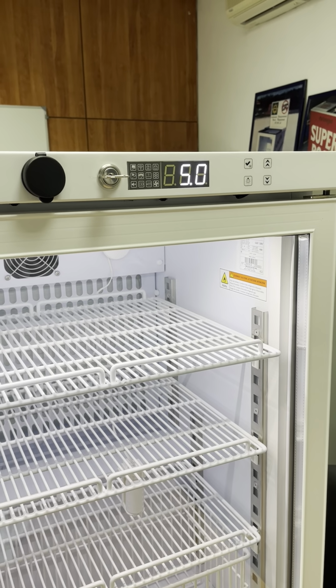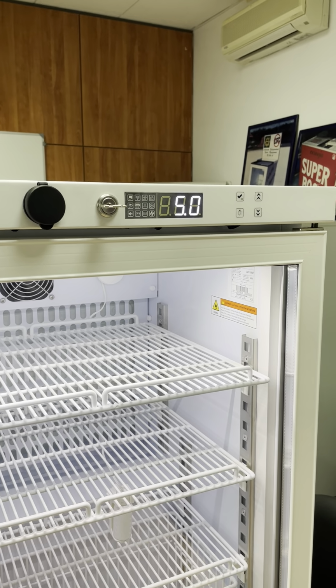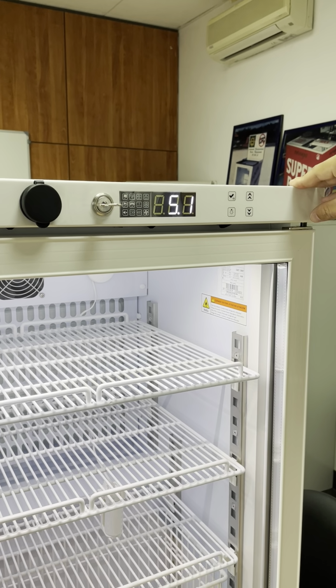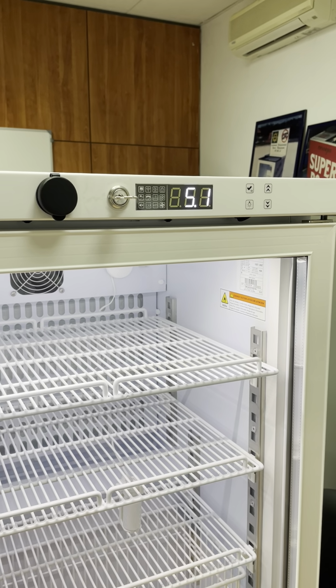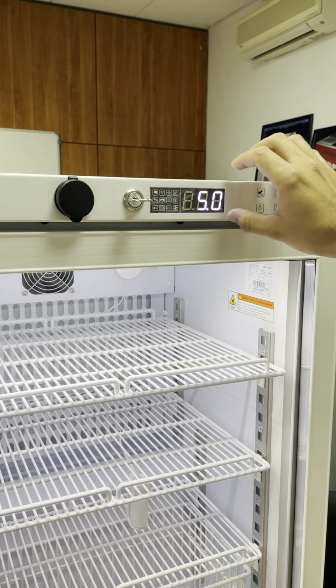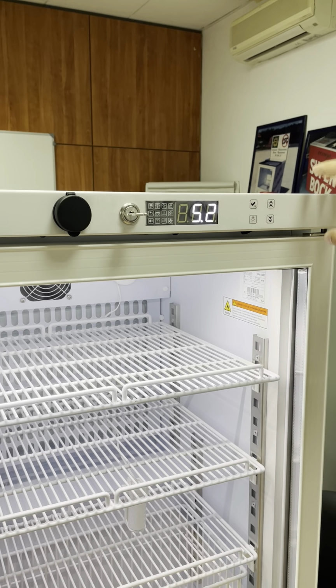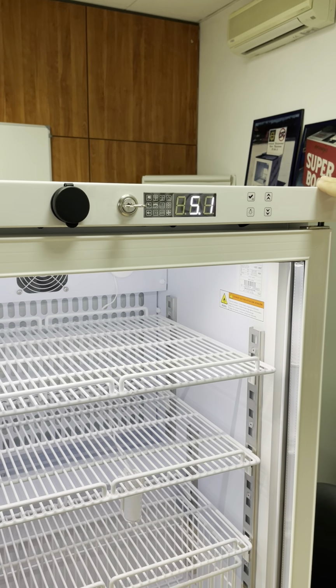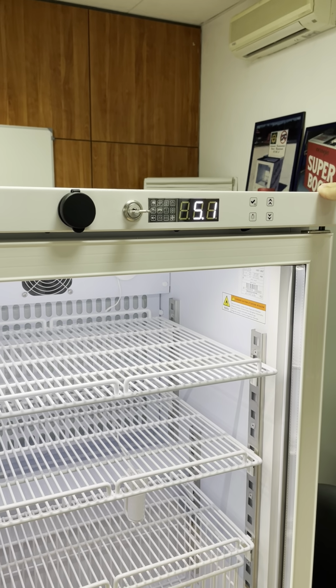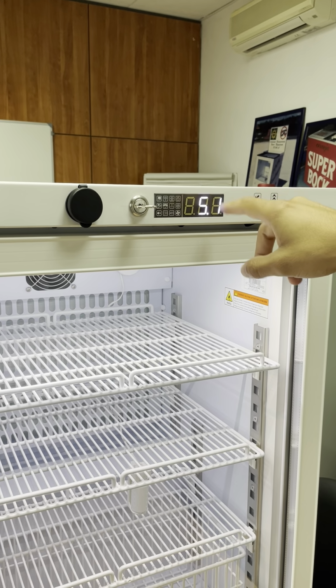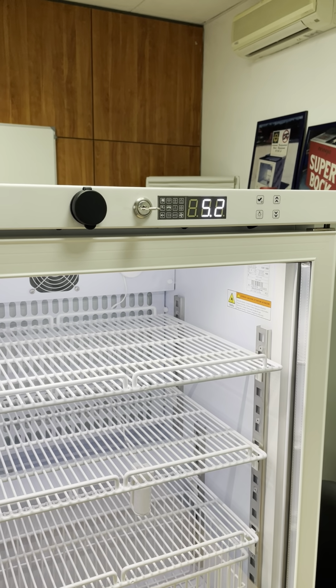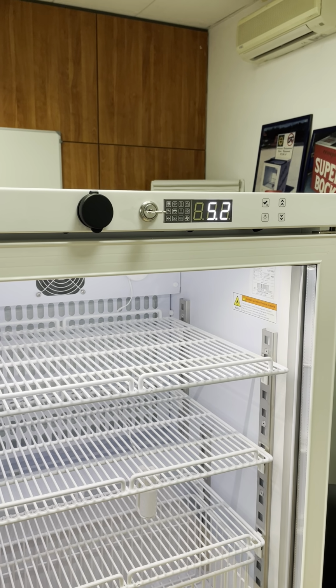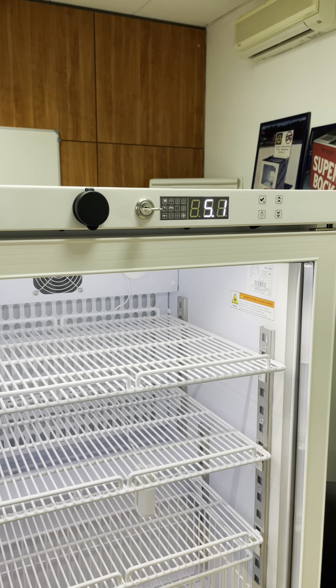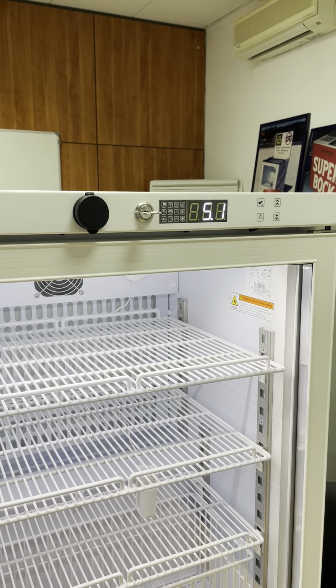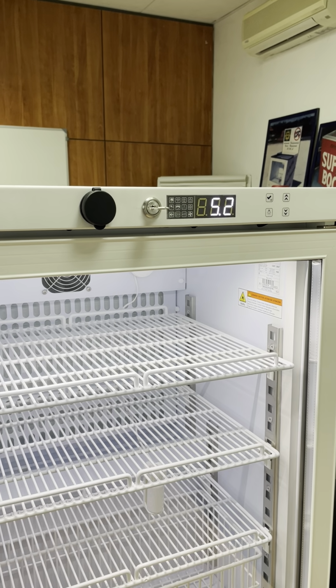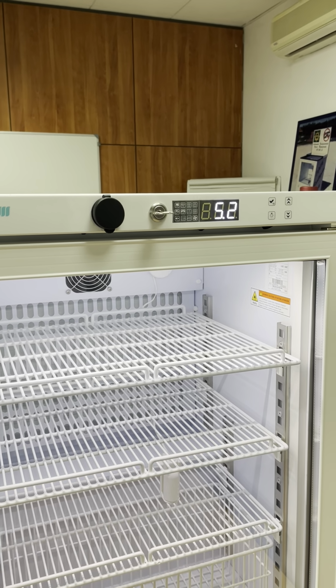So another thing that you can do, and I will show you a power failure, meaning this equipment has a battery. The battery will keep the controller, not the equipment, just the controller, working in case of power failure. So imagine that there is this power failure during the night. This battery will keep the controller recording all the temperatures, so you can know if there is a problem or not. Maybe it was a 5 minutes energy loss, or it can be 2 or 3 hours, and this will keep these recordings so you can see if you need to do something on the medicines or not.